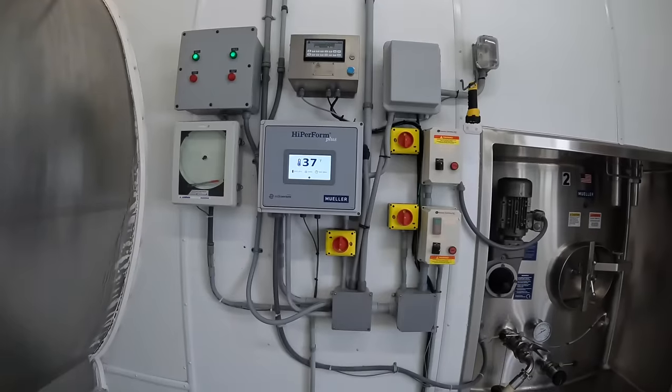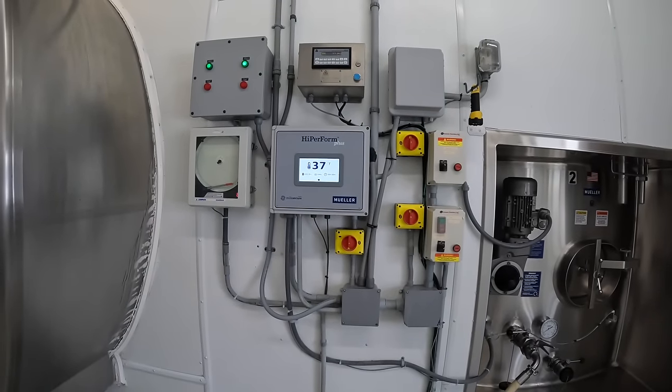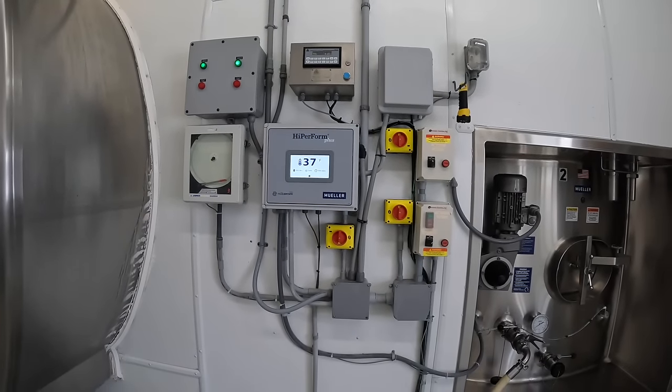It's just after lunch here now. I thought I would check in on the milk silo here. It's showing 37, been bouncing between 37 and 38 in the couple minutes that I've been in here. I did go look at the compressors. So we've got 6 compressors that go to our chiller, that go to our plate cooler. 2 of them come on as stage 1, then there's 2 that are stage 2, and then a single stage 3 and a single stage 4.